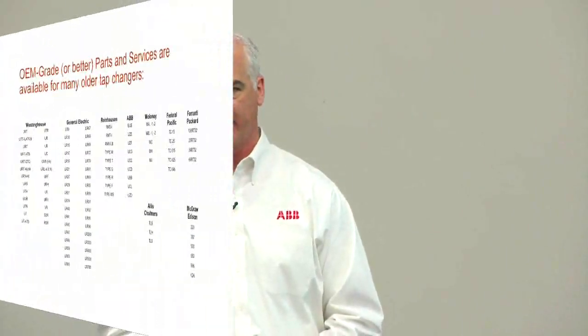Again, we talked about an experienced LTC specialist. When you perform an LTC upgrade, it's always a customized recommendation. Advanced planning, I just talked about that. Uprating potential: we talked about the detailed knowledge of a transformer design, which gives us that ability. But that's something separate from just doing a retrofit. We can look at the transformer and do a retrofit, but if we're asked to do an uprate, that's another step in the process that we have to run through our engineering group, which takes time as well, before you can do the LTC quote. So sometimes that can delay the process while determining whether there is even potential for an uprate.